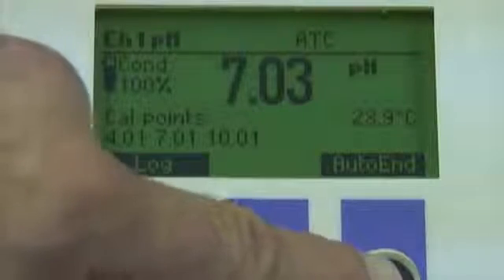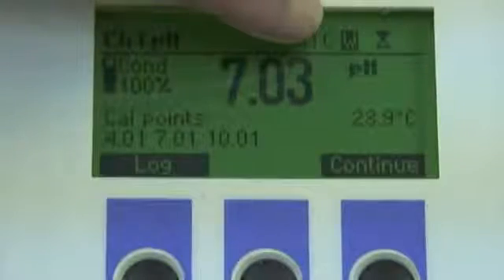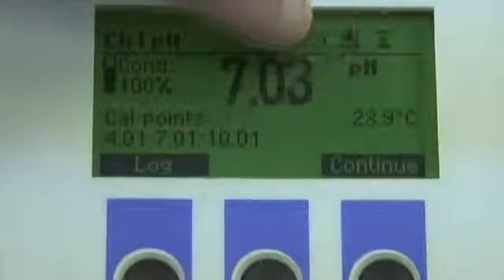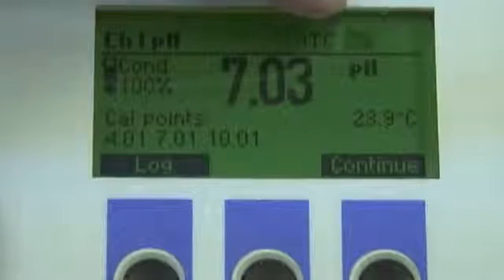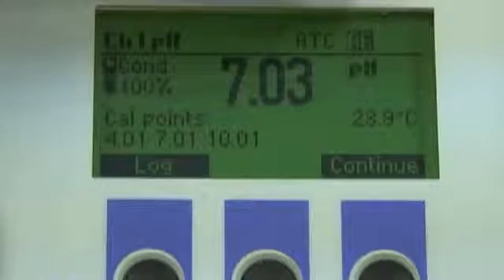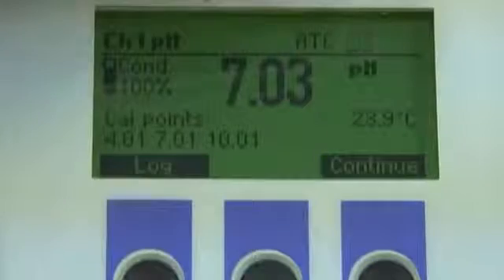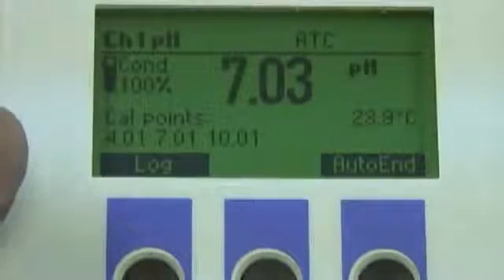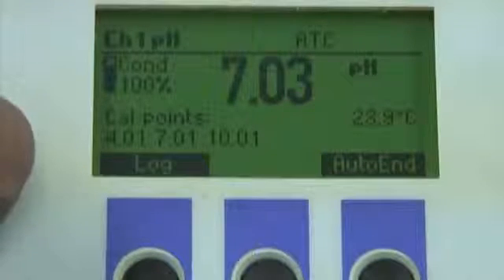And then another feature we have is auto end. So when I push the auto end button, it tells me to wait. We see the stability indicator. And once the W disappears, AE will flash and the reading is locked in. Now this won't change regardless of the solution that I put the probe into, and this is useful with a gas sensing ISE where the readings will continually change. So I'm going to hit continue to go back into the meter mode.